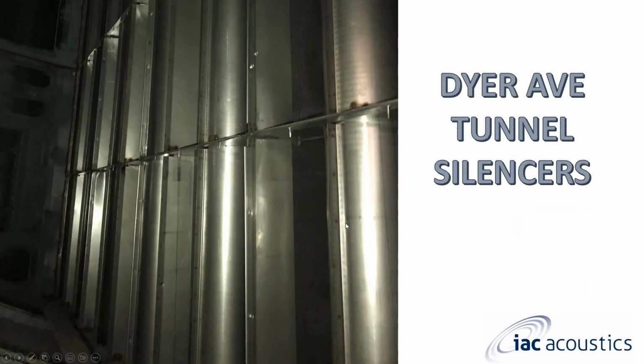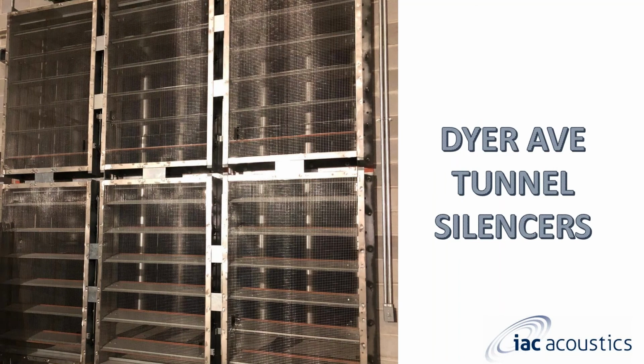Dyer Avenue tunnel silencers, you can see that these are stacked and nested. On this specific tunnel, it was 144 inches tall and 168 inches wide, meaning this is done in multiple silencers that are nested and stacked together. You can see how everything is either crimped together or bolted together to create one large silencer bank. And here is another pictorial of this where the screens have been installed in front of it. And you can see the inner baffles running up and down vertically all through the screen, creating one large bank of silencers.